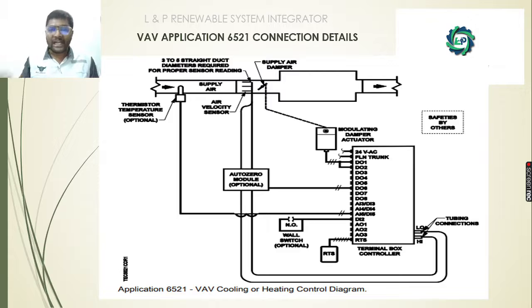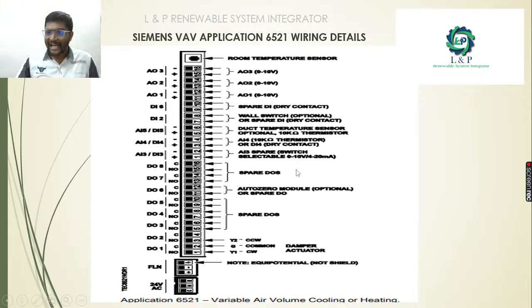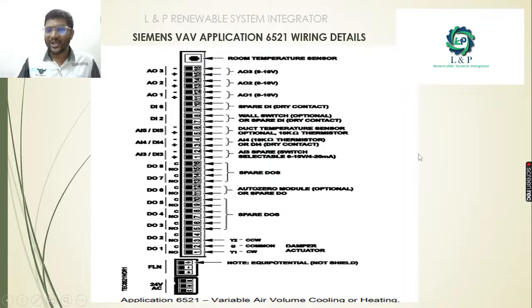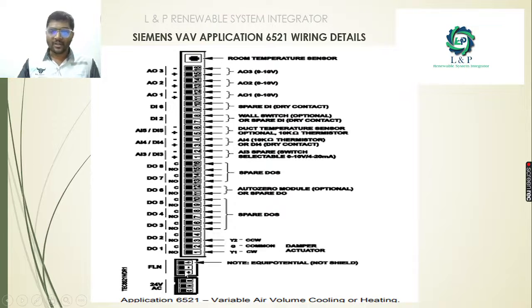Connect the room temperature sensor to the RTS ports, and if you have air velocity sensor tubes, connect them to the tubing connections. For input signals, there is a selectable switch inside these controllers to switch between 0–10V and 4–20mA. If you are choosing a 0–10V temperature sensor, connect it directly and ensure the selector switch for analog input selection is in the correct position. If you plan to use a 4–20mA sensor, change the selector switch accordingly. Other connections include 24V AC, communication wiring, damper actuator connections, and most importantly the duct temperature sensors.